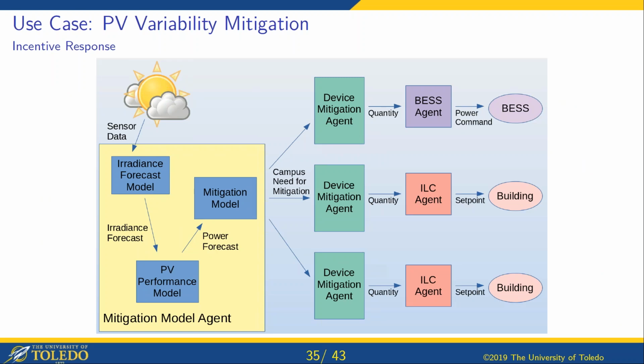It'd be much more efficient if we can, say, use that power somewhere else or reduce a different load. But the PV inverters are very quick to change, whereas a spinning turbine has a time constant that takes a long time. So we've worked with a few different PV variability mitigation algorithms.